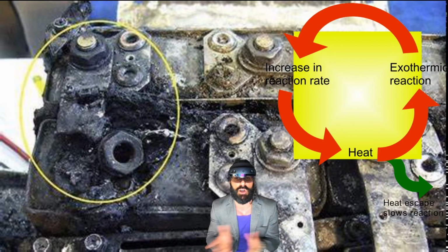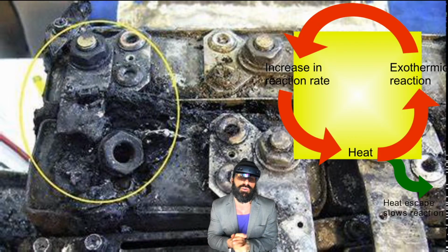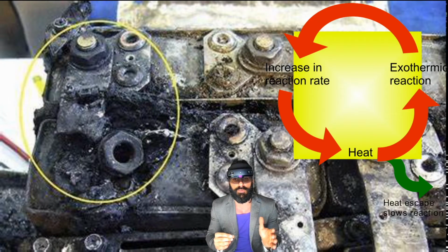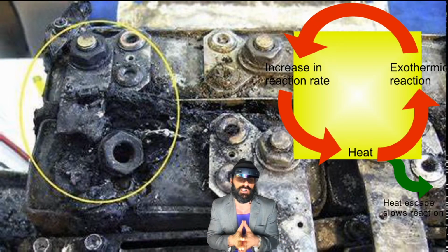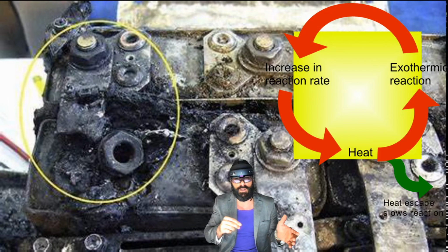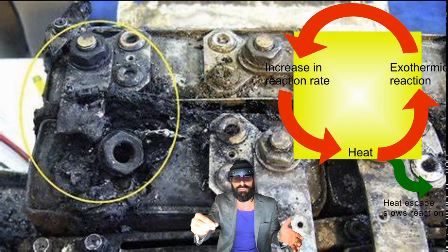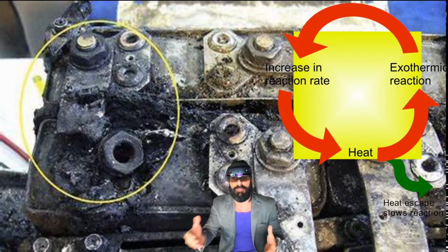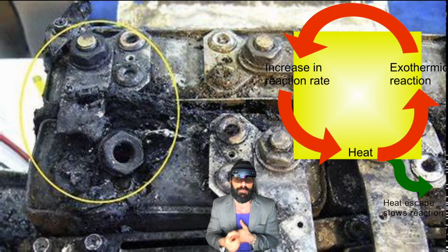And we previously talked about, in volume 2, tripping the breaker mechanism using a shunt. And I had a great question that somebody had asked: where do you install the shunt? Well, the shunt would be installed over one of the inter tiers. So if you had 40 12-volt monoblocks, a 540 volt DC bus, each of the inter tiers would be on inter tier 4 or 8 or 12 or 16. You could put a large shunt in series, going from the negative of 4 to the positive of 5, and then you would calibrate that appropriately and have it come into some kind of a microprocessor or a microcontroller.